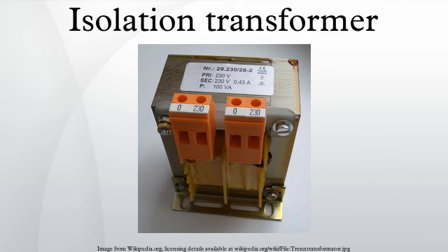Without it, exposed live metal in a device under test is at a hazardous voltage relative to grounded objects such as a heating radiator or oscilloscope ground lead. With the transformer, as there is no conductive connection between transformer secondary and earth, there is no danger in touching a live part of the circuit while another part of the body is earthed.